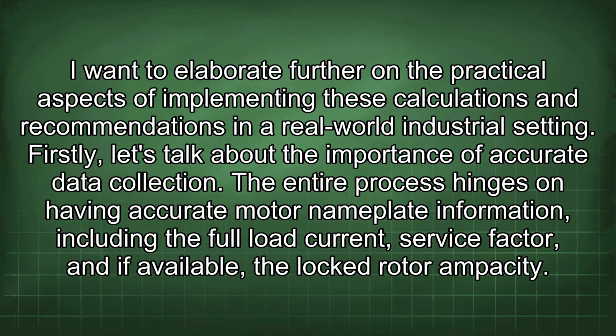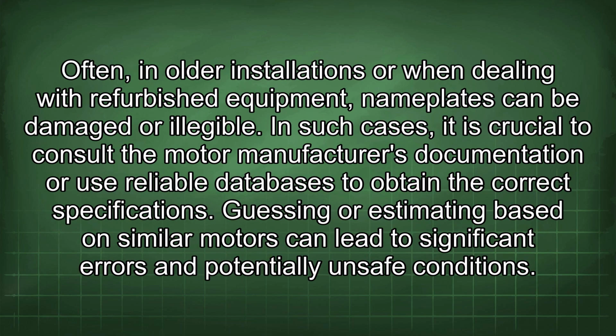I want to elaborate further on the practical aspects of implementing these calculations and recommendations in a real-world industrial setting. Firstly, let's talk about the importance of accurate data collection. The entire process hinges on having accurate motor nameplate information, including the full load current, service factor, and if available, the locked rotor ampacity. Often, in older installations or when dealing with refurbished equipment, nameplates can be damaged or illegible. In such cases, it is crucial to consult the motor manufacturer's documentation or use reliable databases to obtain the correct specifications. Guessing or estimating based on similar motors can lead to significant errors and potentially unsafe conditions.